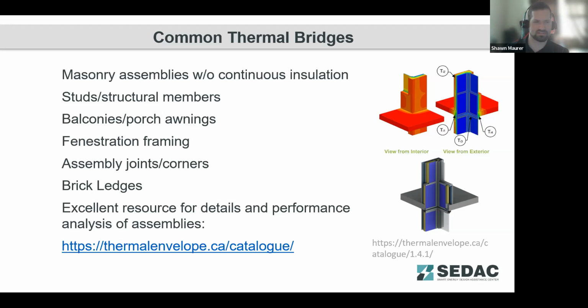Making sure there's that continuous insulation behind studs and structural members, as those are common thermal bridges. With steel framing in particular, when you're looking at the insulation value between steel's framing members, that rated insulation value gets cut by 60 to 70% just because of the high conductivity of metal framing members. Balconies and porch awnings are really common thermal bridge. You've got that concrete slab that comes all the way out to the outside. It acts like a radiating fin.